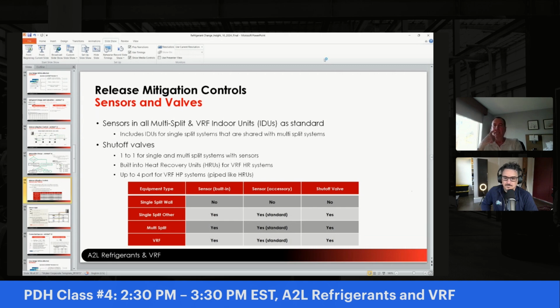What the heat recovery units do is basically allow us to heat and cool a building simultaneously, because you run 3 pipes into them and then you've got 2 pipes coming out to your indoor units. So if you've got a heat recovery system, we're going to have these valves built into these units. And I think we're also going to have the HRUs available without the valves, where you could save a little money if you don't need them in certain areas. And then we're not just going to have these one-to-one single port shut-off valve kits. We're going to have 3 and 4 port boxes also. And those will just be piped like heat recovery units, but you'll just use 2 pipes all the way through instead of 3. So all of our stuff is going to have a sensor built in, and we're going to offer these shut-off valve kits ourselves as an accessory.